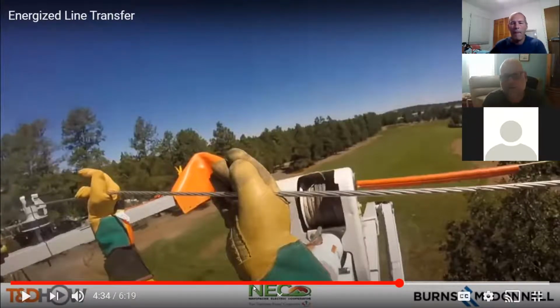Our rule was that if when you cover up on an arm, the phase is going out, you probably had to have 3 to 5 hoses out each direction. Could not see any conductor, any kind of metal, any kind of hardware that you could come in contact with up under those blankets. So you need to cover the insulator, you need to cover the wire, and you need to cover the whole dead end right here. Obviously it's right behind the boom. We can't see it right now, but it needs total coverage.